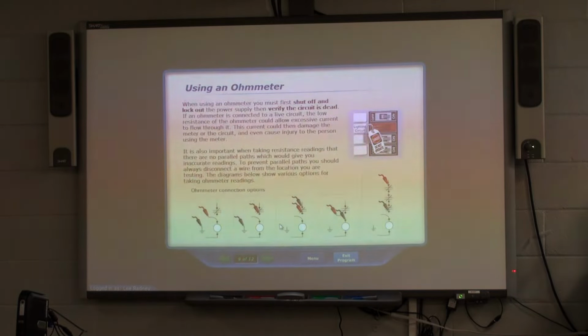And using an ohm meter, we should shut off, lock out, and make sure we're dead before we start taking readings with the ohm meter. That just keeps us from being harmed by what can happen when the meter receives voltage in the ohm setting, and from harming our ohm meter.